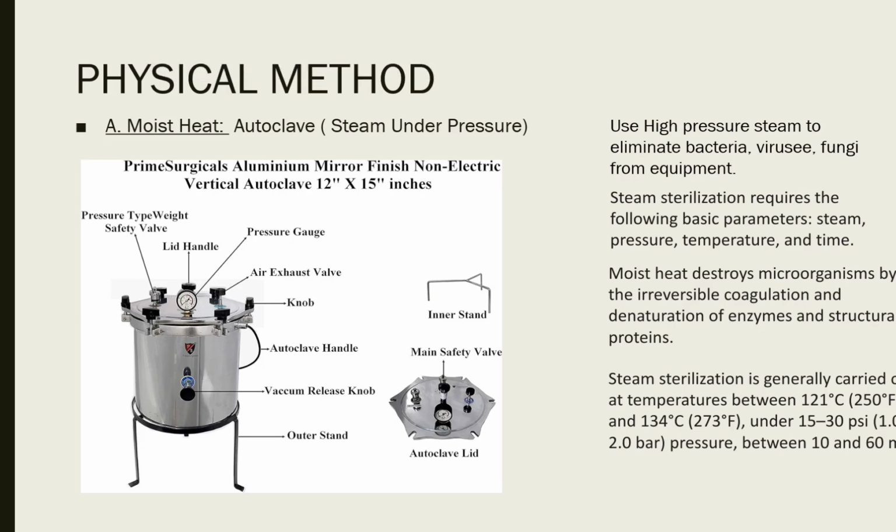So it uses high pressure steam to eliminate bacteria, viruses, and fungi from the equipment. This sterilization requires different parameters, as I have said: steam, pressure, temperature and time. It destroys microorganisms by irreversible coagulation.